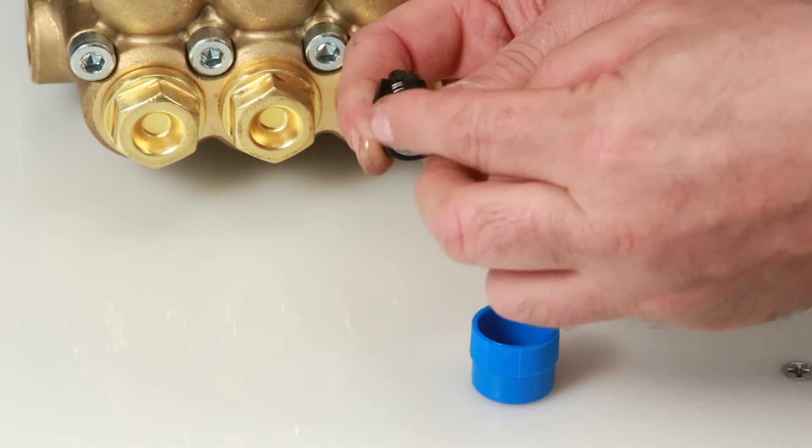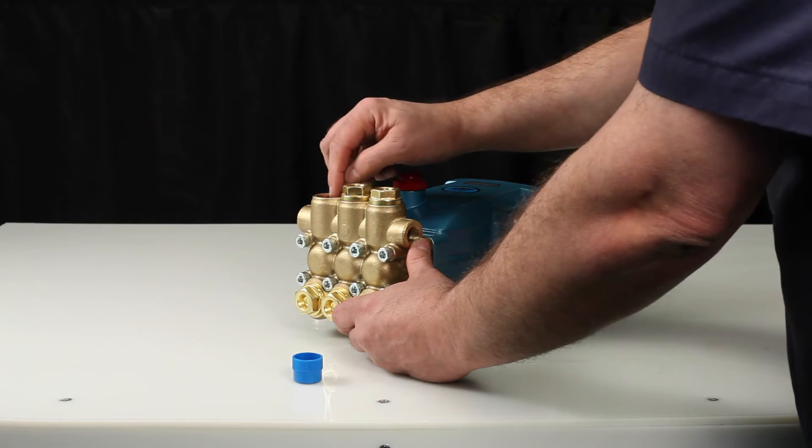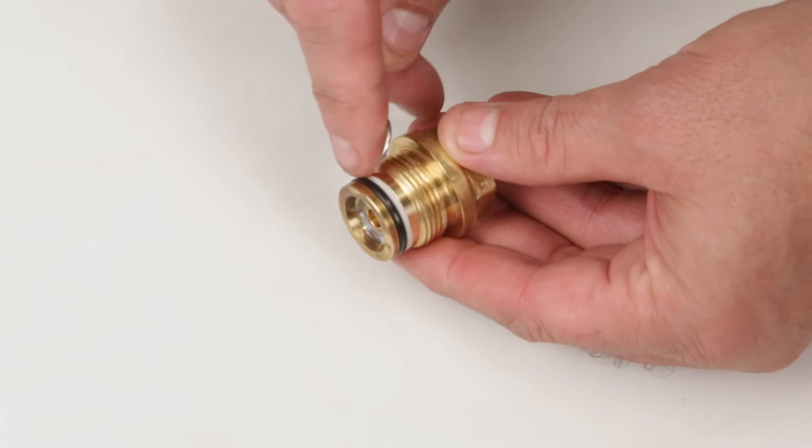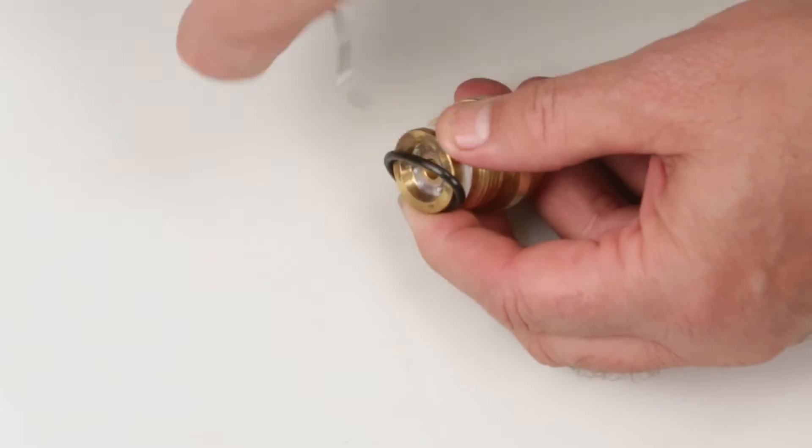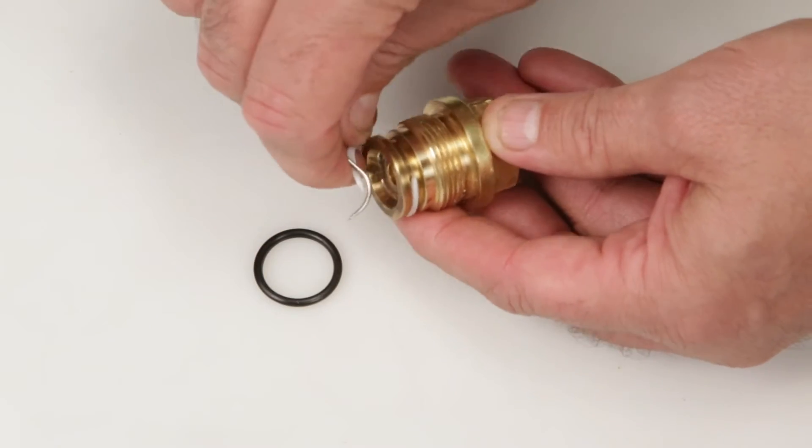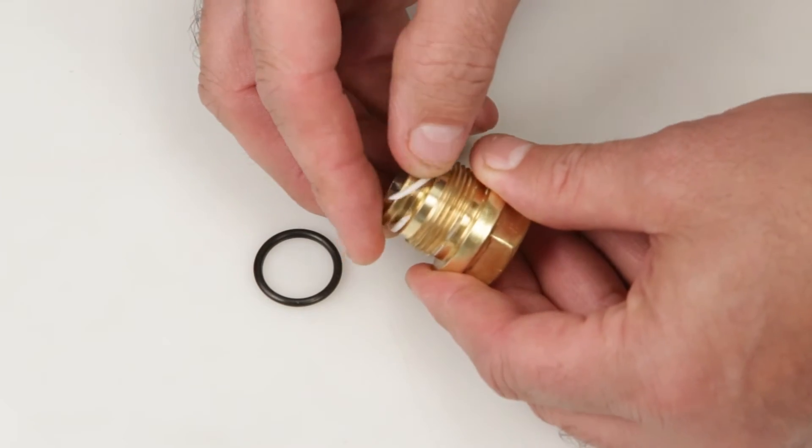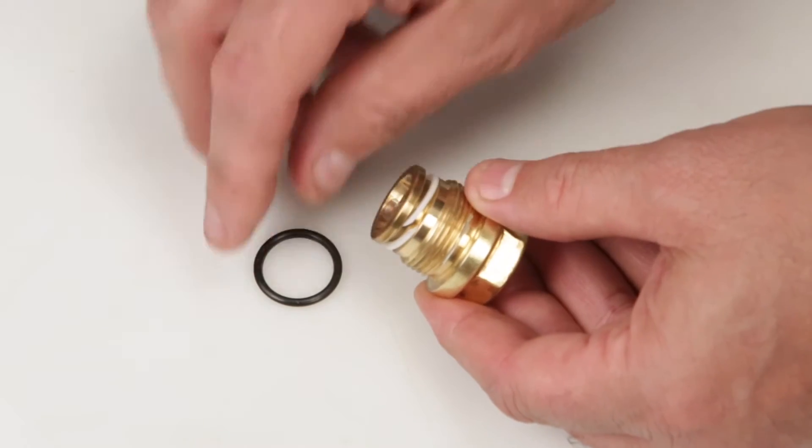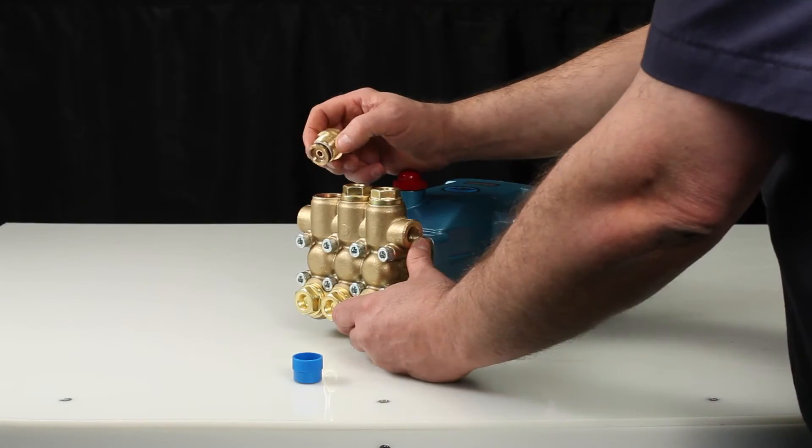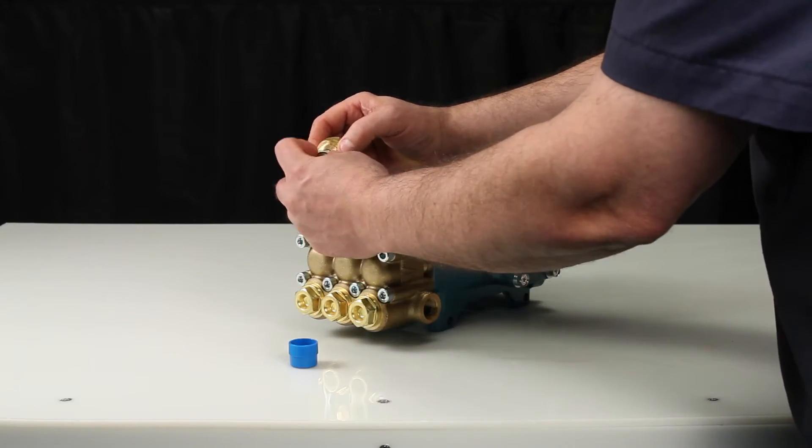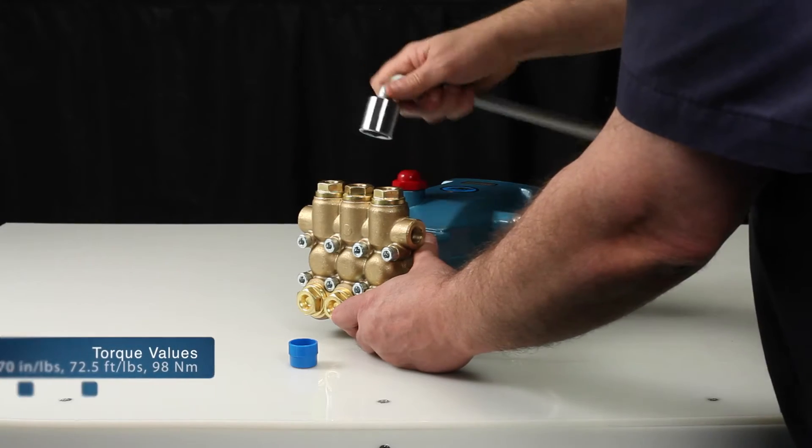Before installing the new valve assembly, lubricate the O-ring on valve seat. Next, insert valve assembly into manifold and press into place. Before reinstalling the valve plug, using a small screwdriver or pick, replace the O-ring and backup ring provided in the valve kit. Lubricate the O-ring and reinstall the valve plug. Torque to specification.